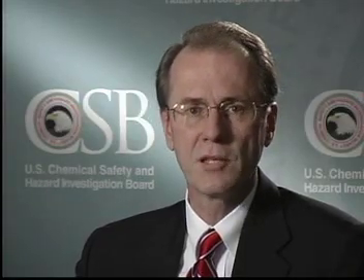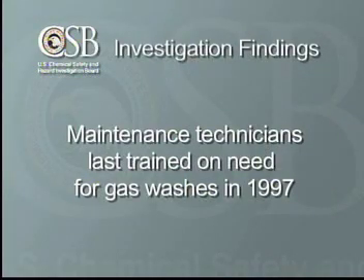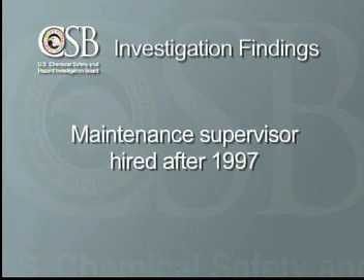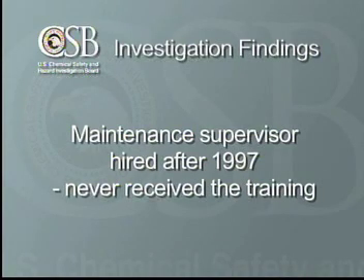Another lesson from this incident is the importance of regular training. Maintenance technicians had last been trained about the need for the gas washes in 1997, seven years before the incident. The maintenance supervisor, who was authorized to use a password to skip the gas washes, was hired after 1997 and never received the training. So a very important lesson is, be sure personnel are fully trained on process hazards before authorizing them to override automatic systems.